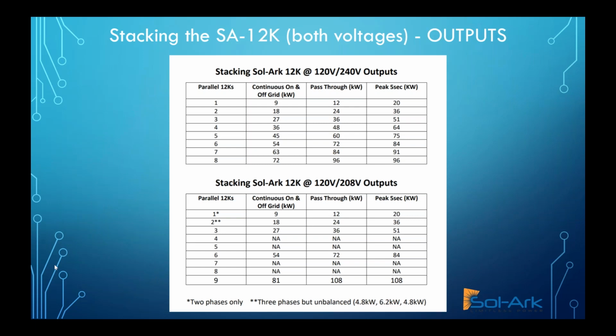So it does break it down in a 120/240 and a 120/208. Just bear in mind when you are looking at the 208, obviously there are some little asterisks there. One system is obviously 2 of the 3 phases. 2 systems does allow you to have 3-phase, but it is imbalanced across all 3 phases. And then 3 and on, you really have to do in multiples of 3 after that. So 3, 6, and then 9 is the max total. Just keep that in mind. There is some great information in the manual that will help you design the system.